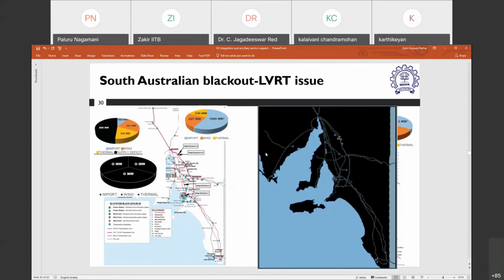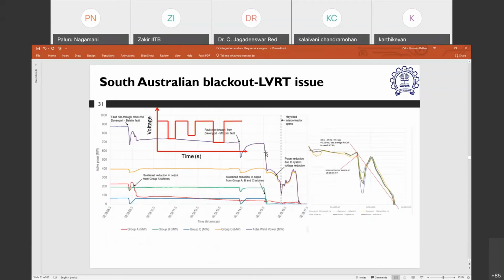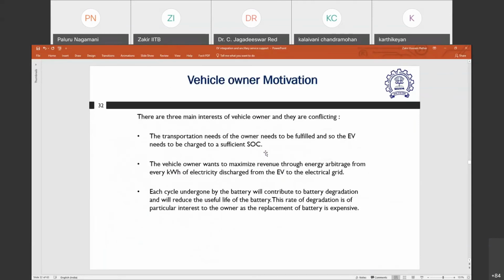Because of the storm in the southeastern grid, there were back-to-back faults in the system and around 6 voltage dips that these renewable energy plants experienced. The LVRT did not actually require to have back-to-back LVRT compliance. So therefore, those renewable energy generators decreased their output power, which increased the import from the rest of the Australian grid through the tie line, and the tie line got overloaded. The tie line was tripped because of the overloading, and the grid collapsed. Now that shows the issue with these renewable energy generators in terms of voltage stability.